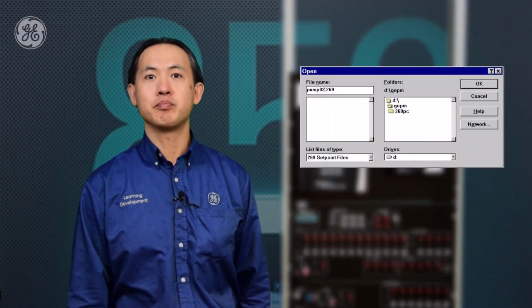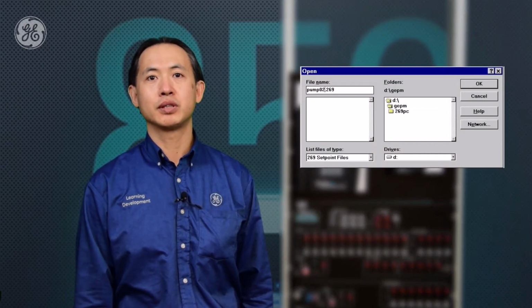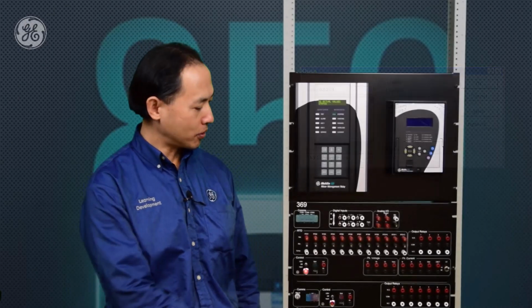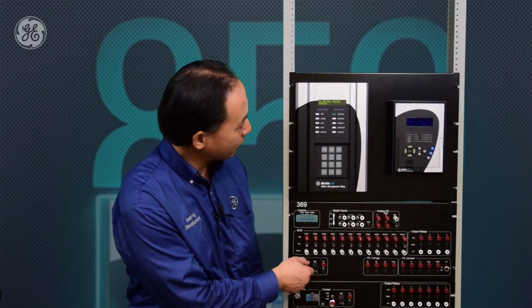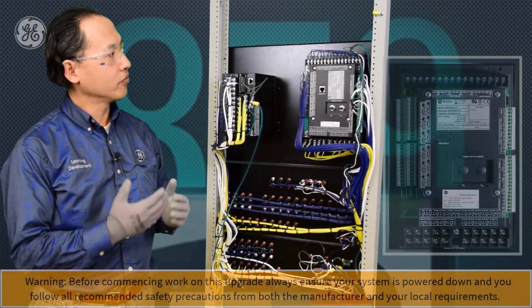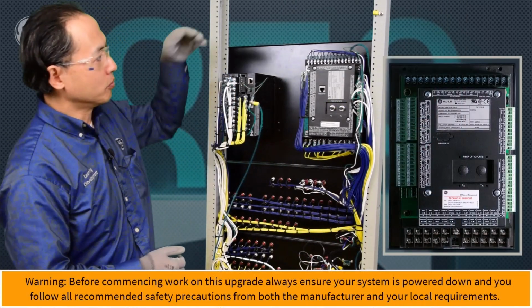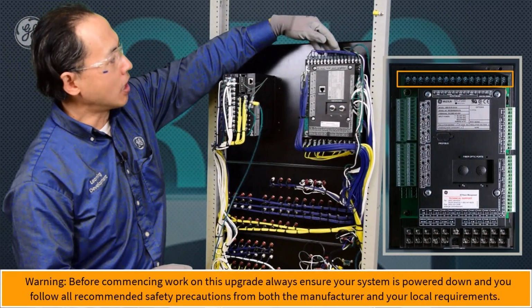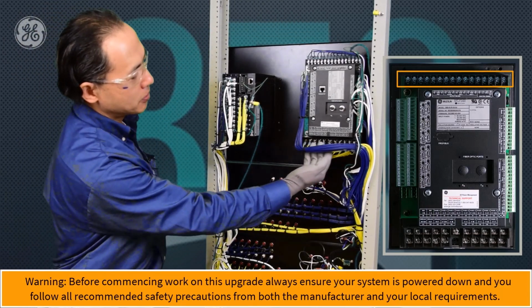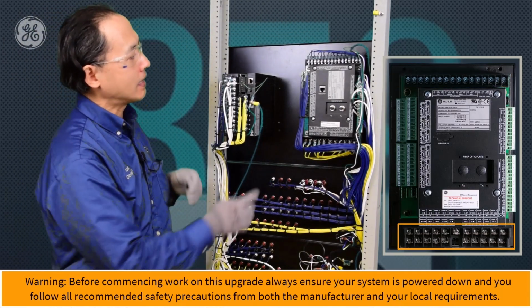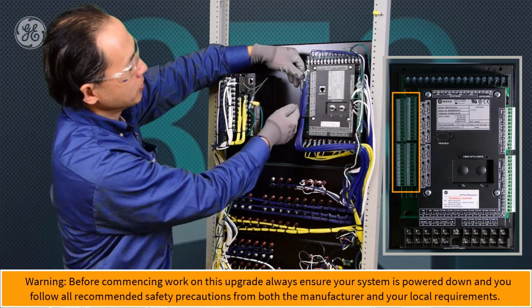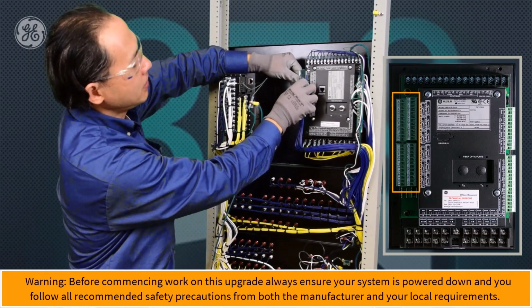For the setting files of the 269 Plus, you need to manually convert them into 859. So now let's power down this relay and remove the wiring from the back. To remove the wiring from the 369, we need to remove the top wiring for the relay outputs and the bottom CT-VT inputs, and then unplug the terminal blocks for the RTDs.